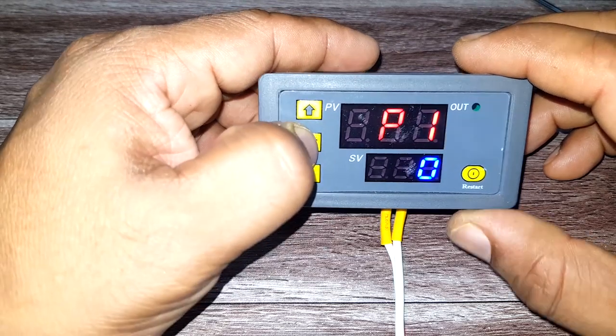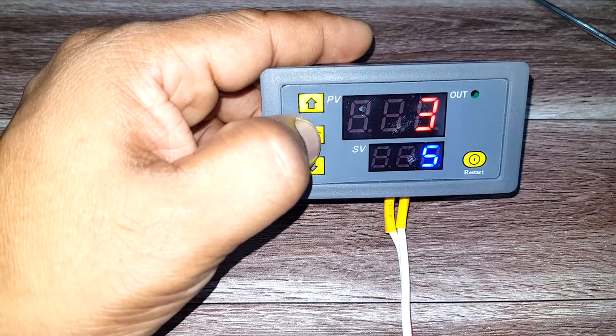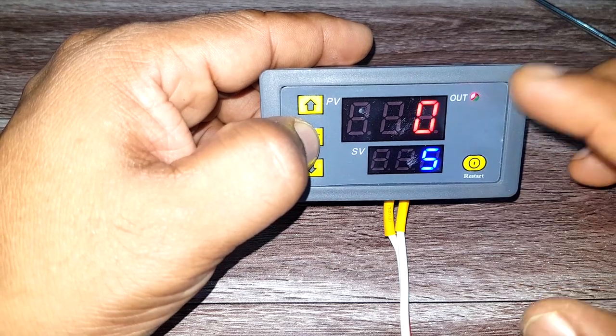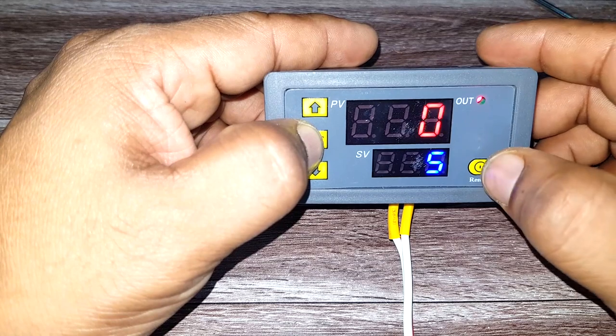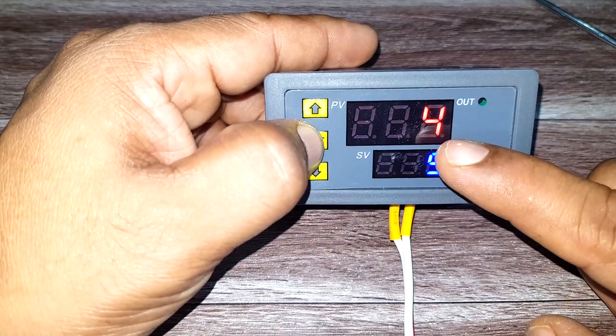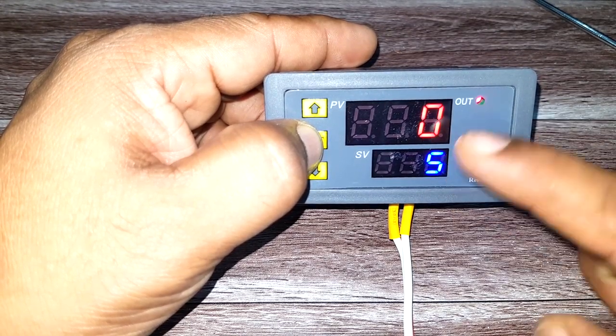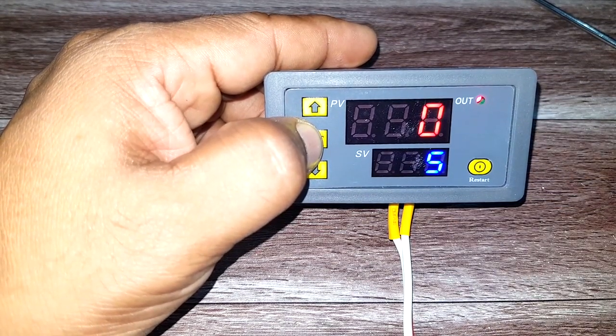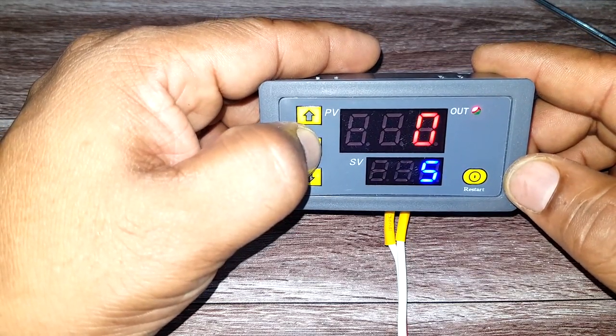Let's go into P1 first. In this mode, the output is off during the red timer. Once the red timer finishes, the output turns on and continues to be on forever. The blue timer data is irrelevant in this mode.